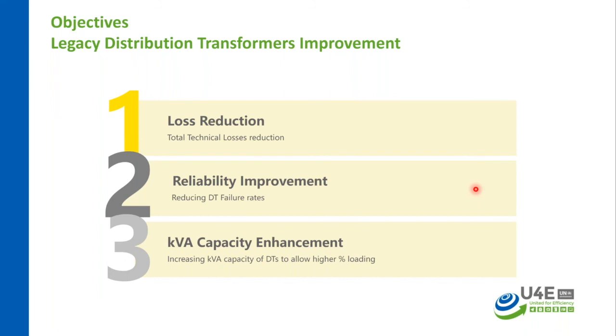Generally, the old legacy transformer improvement KPIs can be for loss reduction, that is, the total technical loss reduction, which is no load loss and load loss. Then reliability improvement by making the transformer hotspot temperature lower or reducing the DT failure rates by including protection devices, etc. And then the third one is the kVA capacity enhancement, where you make the transformer suitable for frequent overloading in order to address the overloading issues.